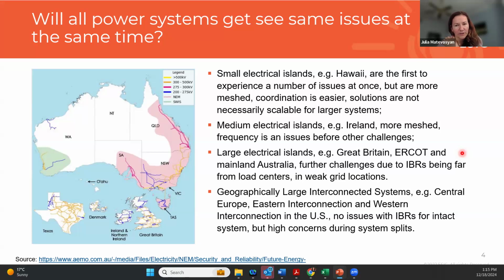Larger electrical islands like Great Britain, ERCOT (the Texas system), or mainland Australia, the first challenge you encounter with integration of inverter-based resources is weak grid conditions, where you have pockets of the grid high on renewables that are far away from load centers, where synchronous generators or strong voltage sources are. Only then does inertia become an issue.